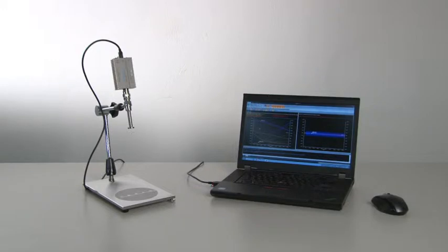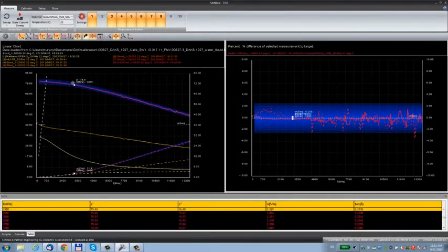In this video, I will show you our new DAK system, the DAKS. The DAKS is a portable, low-cost, easy-to-use and plug-and-play system that includes the R140. For high-precision measurements, when the portability is not required, and especially above 5 GHz, use the DAK probes.